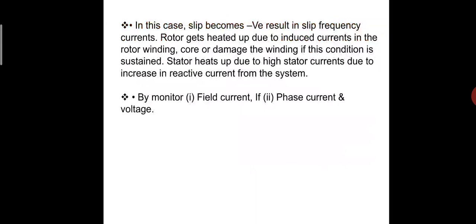In this case, slip becomes negative, resulting in slip frequency currents. The rotor gets heated up due to induced currents in the rotor winding, which may damage the core or the winding. If this condition is sustained, the stator heats up due to high stator currents, due to increase in reactive current from the system.